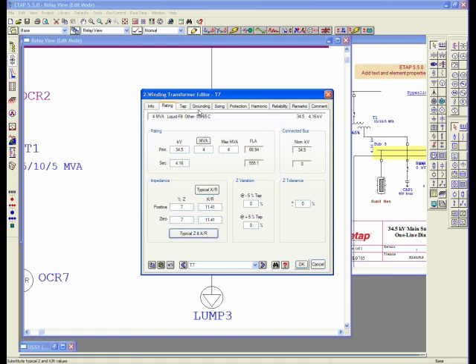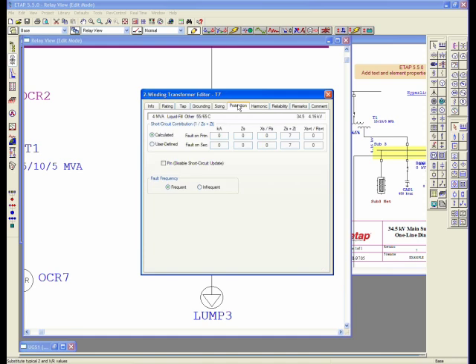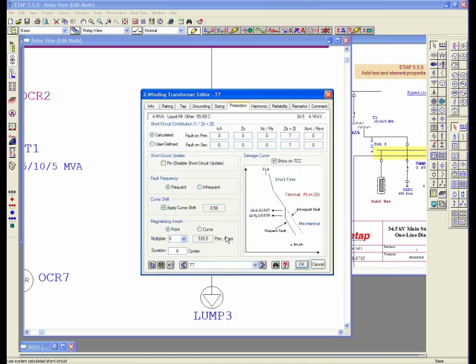Let me put a 4 MVA transformer with typical data. And here, for the transformer, we have quite extensive information about the short circuit information, that if you run the short circuit study, you could get the system impedance on the primary or secondary side, or you can specify your own impedance information for the system side.